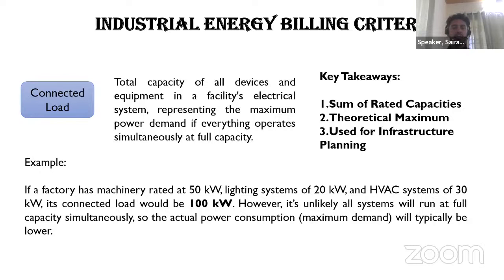For example, consider a factory that has machinery of 50 kilowatt load, a lighting system of 20 kilowatt load, and an HVAC system of 30 kilowatt. Together, the connected load will be 100 kilowatt. But all these equipments won't be running at all times. They may operate at 50 kilowatt plus 20 kilowatt, or 20 kilowatt plus 30 kilowatt, or 50 plus 30. So the maximum demand that can be reached at the site, if you operate the machinery and HVAC, will be 80. So it helps in determining the contract demand.